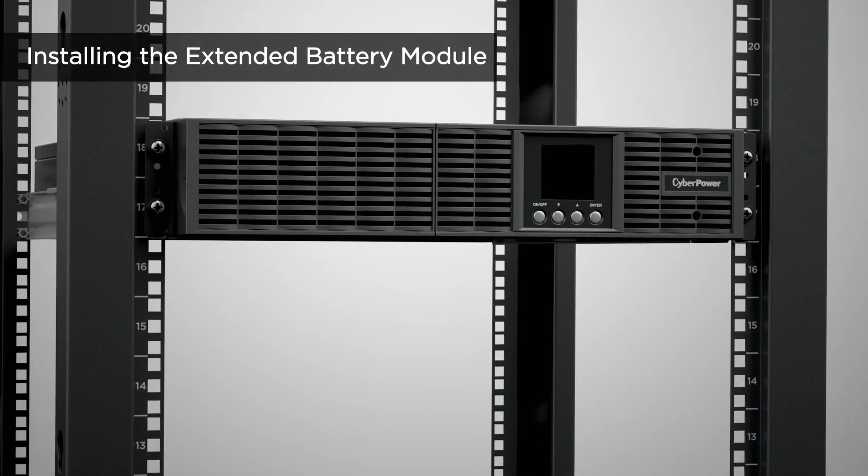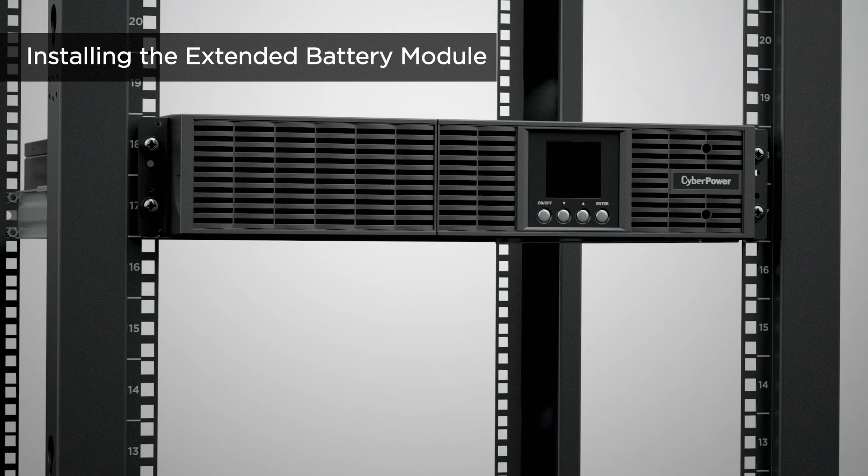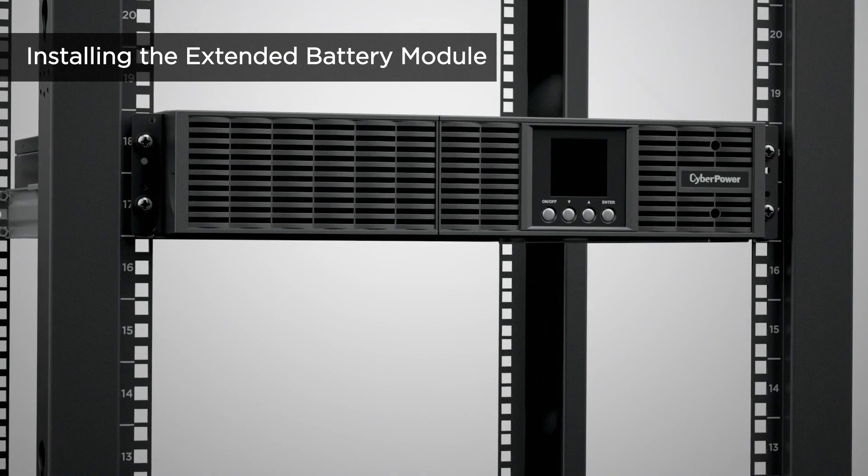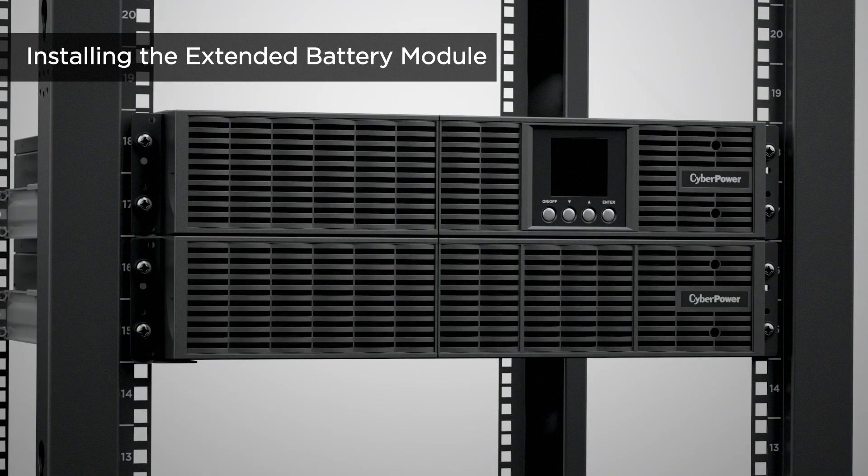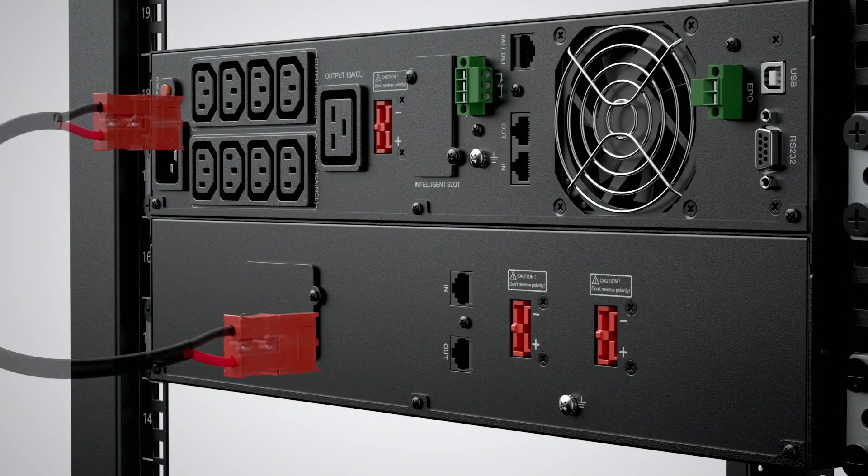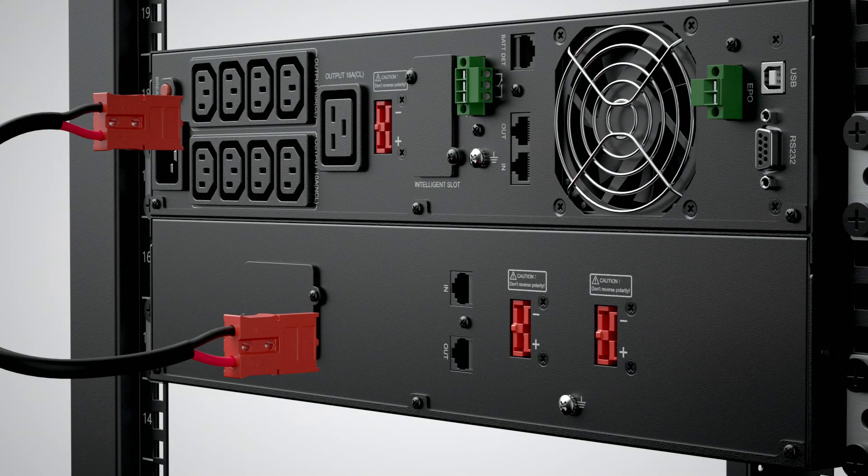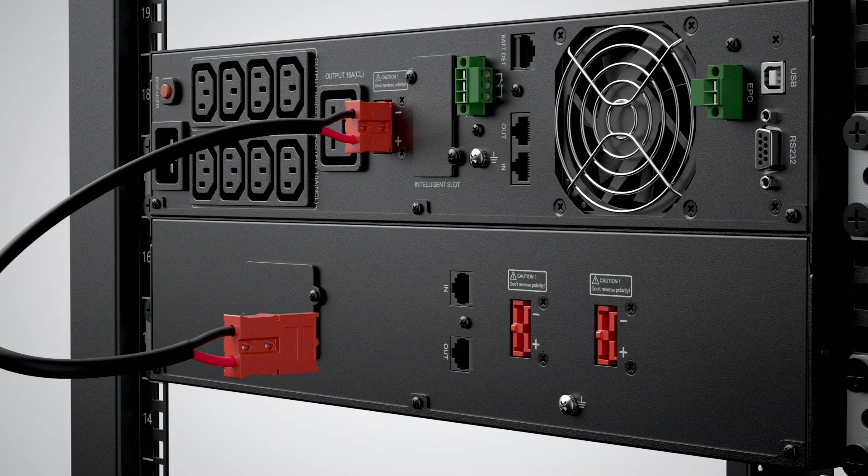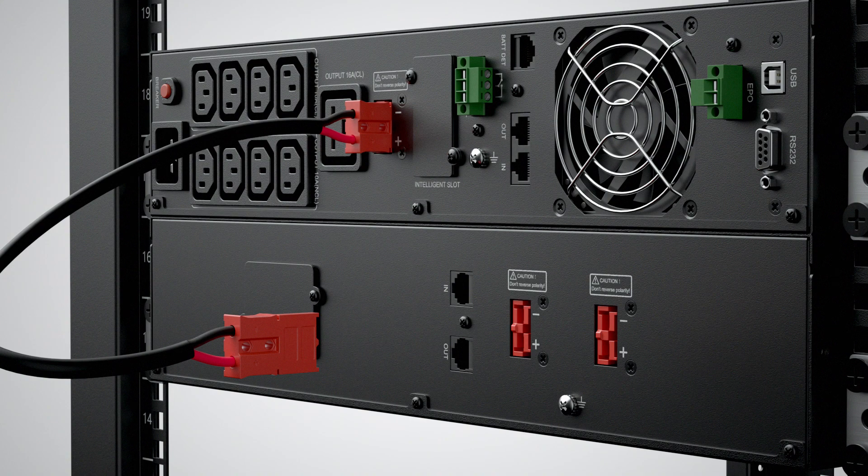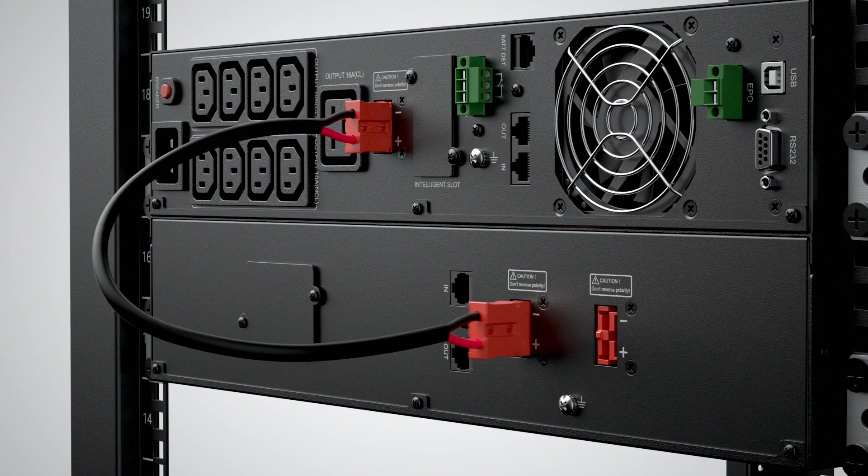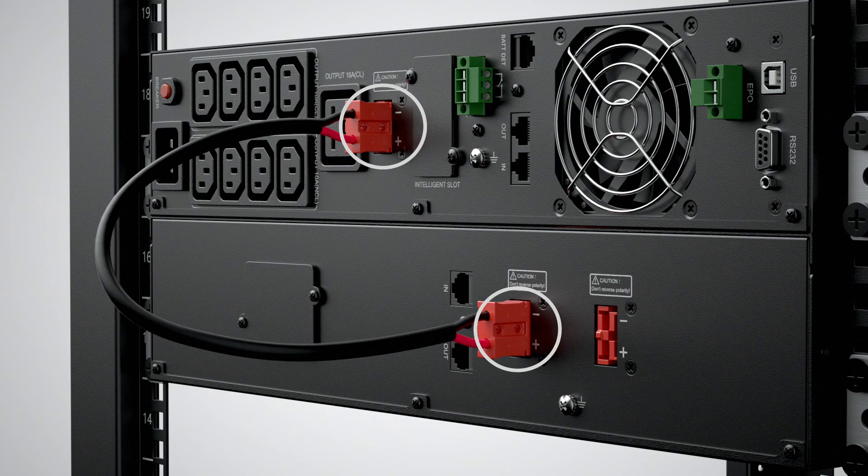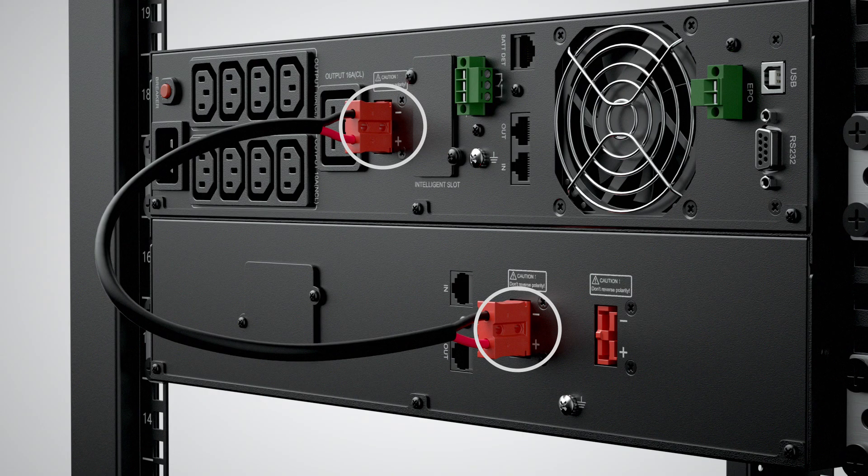To use the extended battery modules for longer power backup, follow the same rack mount installation procedure. Connect the battery cable to the battery connector of the UPS and to the input connector of the extended battery module, making sure the polarities correspond with each other.